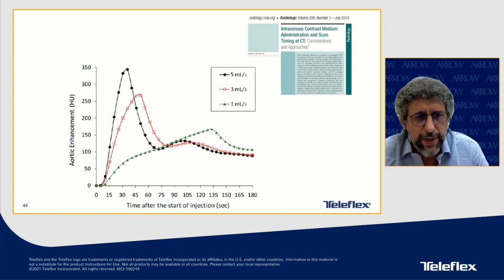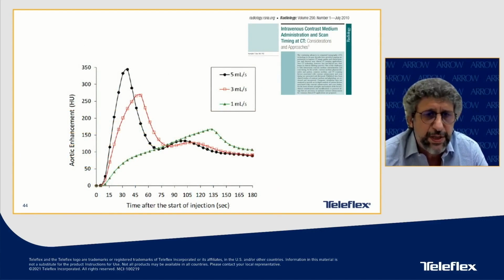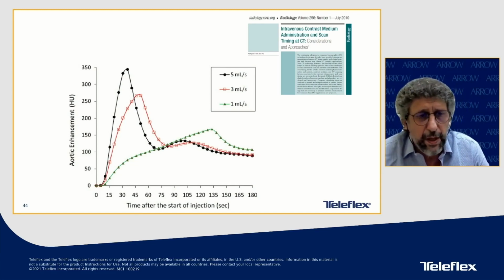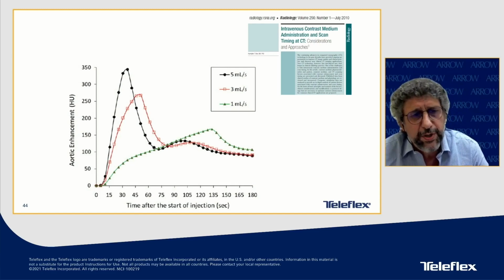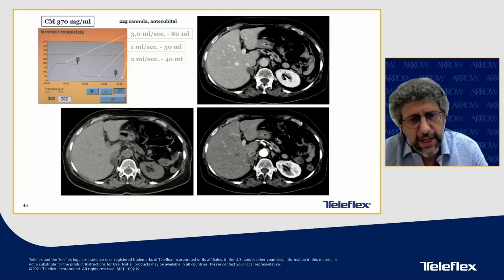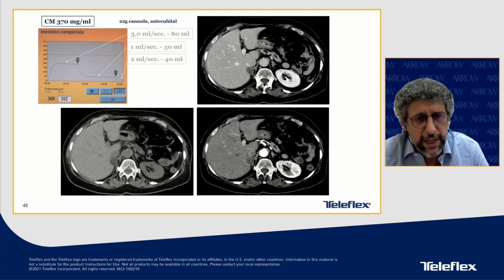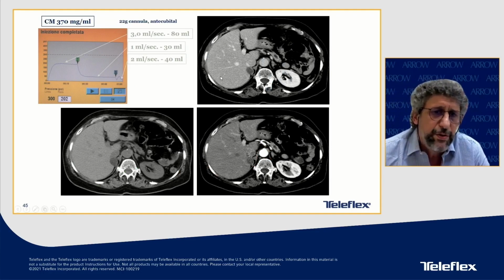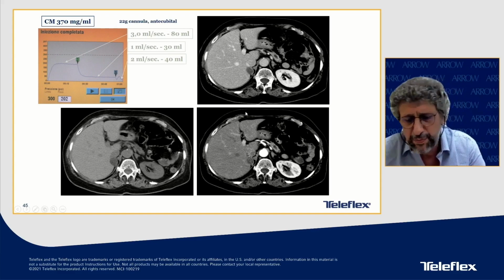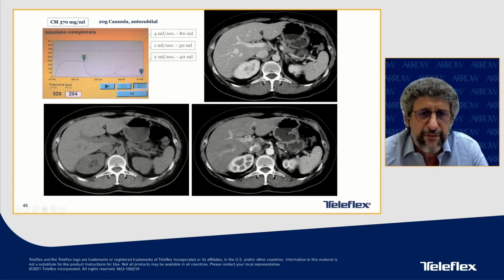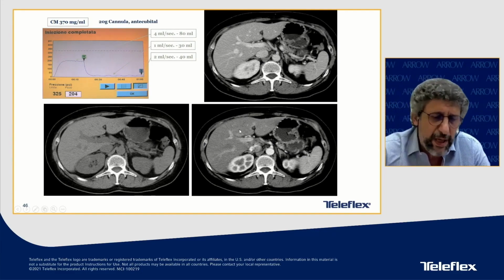This is what happens when we inject contrast media at different flow rates. As you can see, at the high flow rates in the black line, the concentration of the contrast media reaches a peak and then decreases rapidly. And this is crucial to have good contrast enhanced images of the parenchymas and to have a good washout in order not to confuse the different phases of the study, arterial, venous, portal and late. You can see here, if we inject a contrast media at a flow of 3 milliliters per second, this is the image you obtain, and this is the image you obtain if you increase the flow rate. So the contrast enhancement of the parenchymas increases.